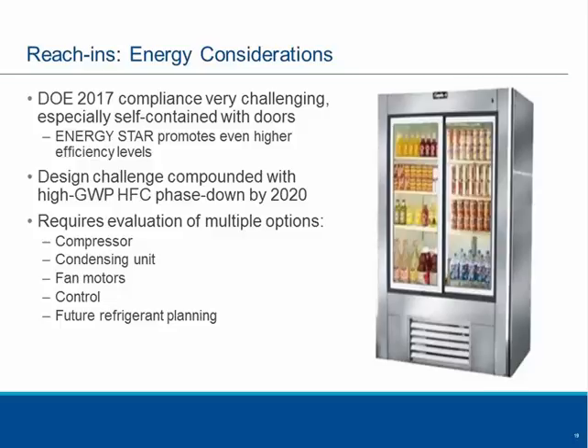webinar. So as I said, for reach-ins and meeting the efficiency levels, it really requires multiple design options. You have to look for efficient compressors that have to be bundled in efficient condensing units to get the most out of the compressors. Certainly, looking at ECM fan motors is an important design consideration. And all of the controls that are wrapped around these units, anti-sweat control, defrost control, how you manage your condensate, all will play a big part in meeting those efficiency levels. And as I already mentioned, future refrigerant planning, some of these refrigerant options can often bump up efficiency in a properly designed system.